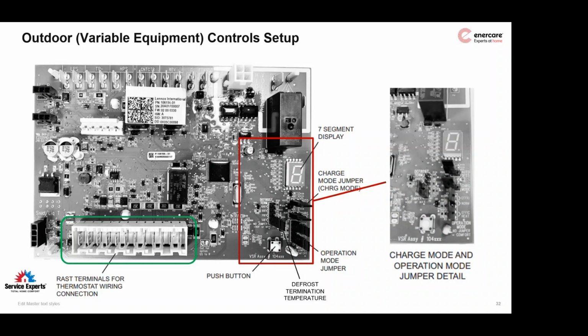So maybe they're connected to a 24-volt system and then later they get upgraded to a fully communicating system and want to only use the 4 wires. Certain portions of that connector still need to be there, or vice versa. If it goes from a communicating system and that thermostat fails on a Friday night, maybe our service technicians need to go out and make it functional for a 24-volt thermostat. Well, then they're going to have that connector. Please make sure that they're left there.